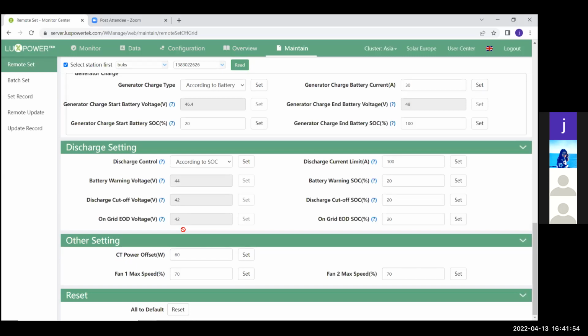So this is to keep the inverter and the backup system able for when there's load shedding, so you can still have a slightly better amount of backup power that's left in your batteries. But if you do this setting, your inverter won't use all of your batteries. You won't save as much electricity, but you will always have a backup amount of power in your batteries.